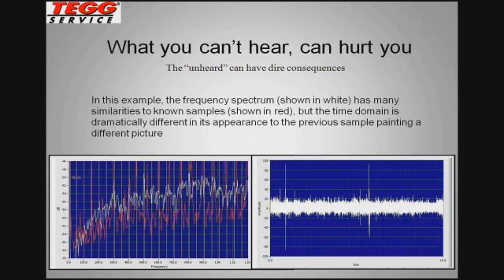If you look right here, in the red, we have a known sample of arcing, as we saw a few slides ago. We overlay the recording that we made on the transformer with that known sample. Although it is not identical in nature, we look for the similarities, or as I called them earlier, the footprints. I'm looking for the first few harmonic frequencies that may occur. Because we're in Australia, the operating system there is 50 hertz, so I got the harmonic cursor set to 50 hertz. And we can see we have some characteristic similarities here.